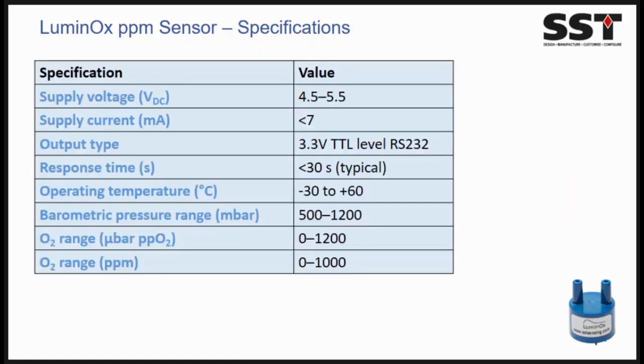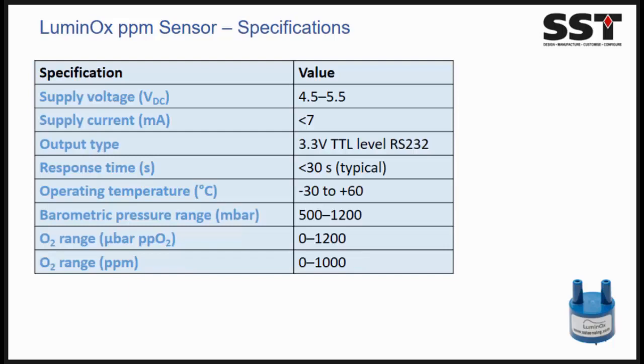So here are just a few of the specifications from the sensor that we are happy to say to date. So I mentioned low power, so at 5 volts, less than 7 milliamps. The response time of the sensor, as you've seen, is less than 30 seconds typically. You have slight variations from sensor to sensor. The operating temperature, again, this is one thing that's really crucial because most ppm sensors, such as electrochemical, go from around about -10 or -20 to about 50 to 55 Celsius. So we're trying to make an improvement on that.